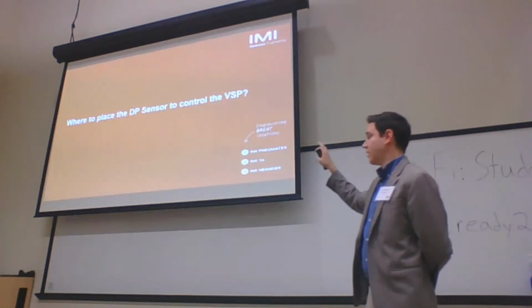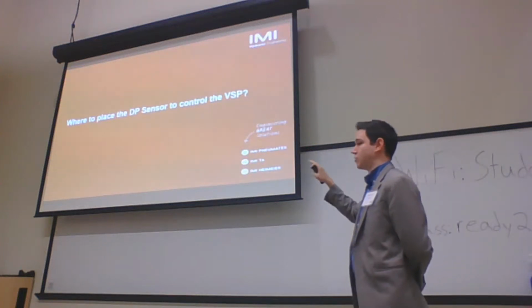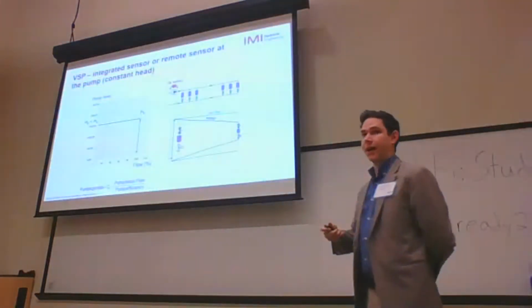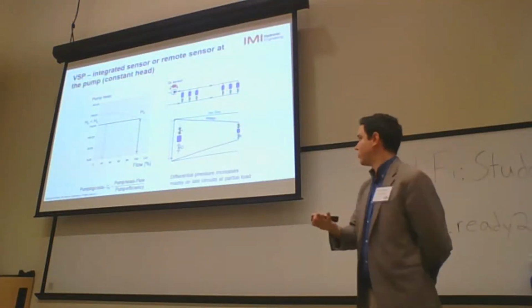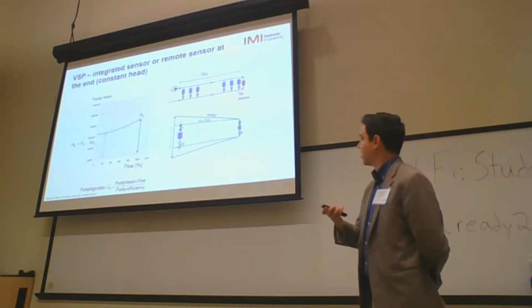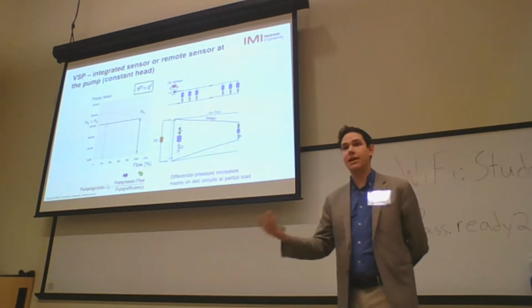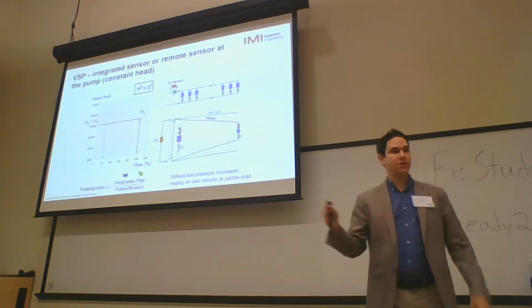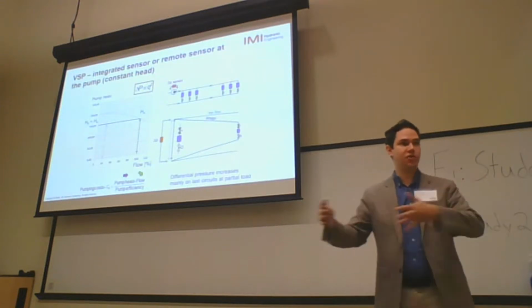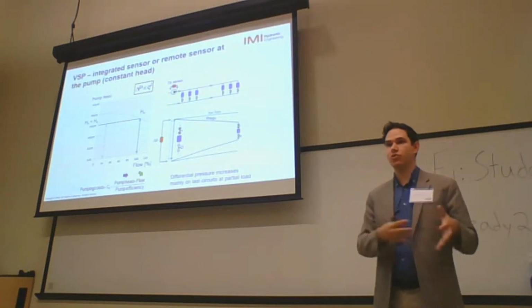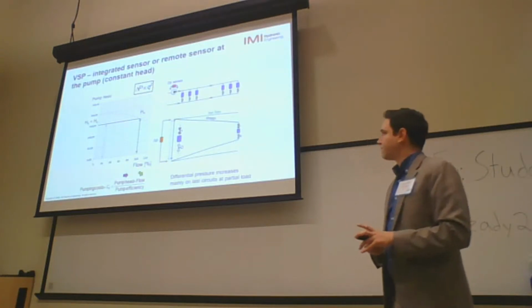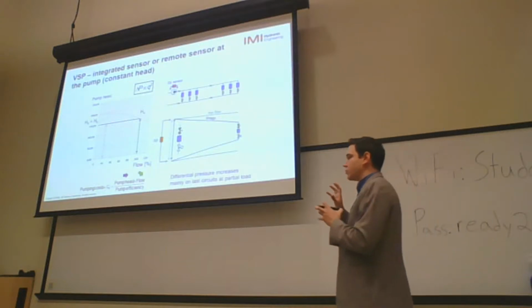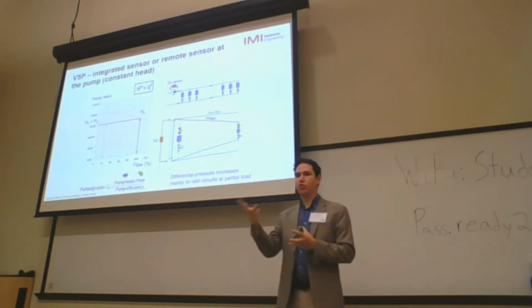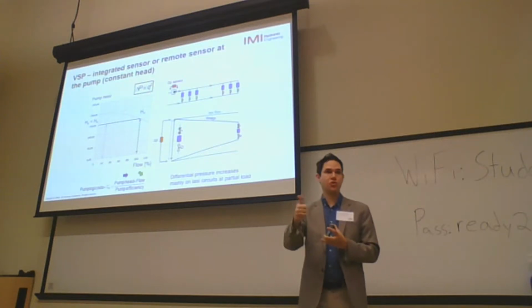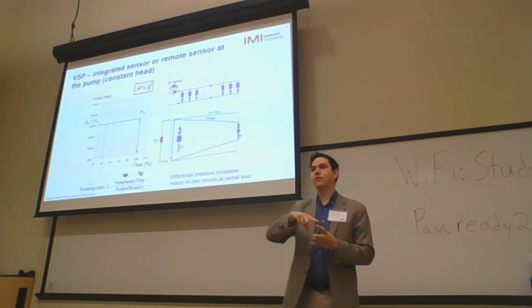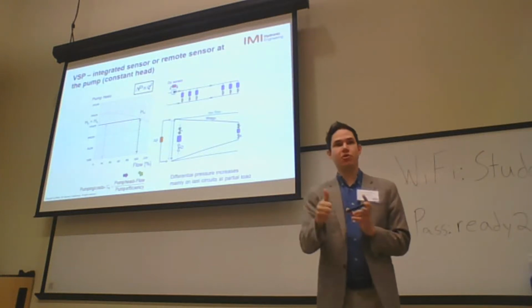And the last topic that I'm presenting today is where to place a DP sensor to control the variable speed pump. It may not be a direct question for some of you, but we got it from some TAB contractors asking us before. I think this question floats around between designers and contractors: where to place the DP sensor to control the variable speed pump. What we mostly hear in the market is the 2/3 rule of thumb: place the DP sensor 2/3 of the way through the installation to control the variable speed pump. Where did the 2/3 rule of thumb come from?